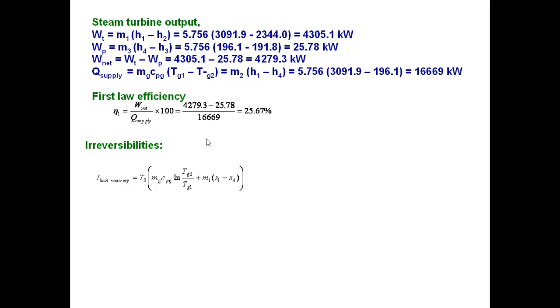The final entropy minus initial entropy we have to take for both hot fluid as well as the cold fluid. After substituting these values, that is temperatures and entropies in the formula, 1722 that is approximately 1.7 megawatts of exergy is destroyed in the heat recovery steam generator.